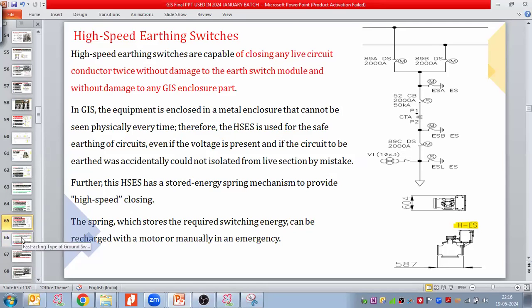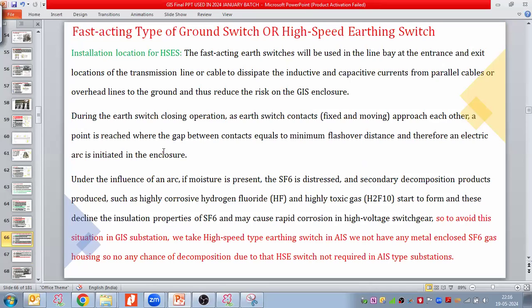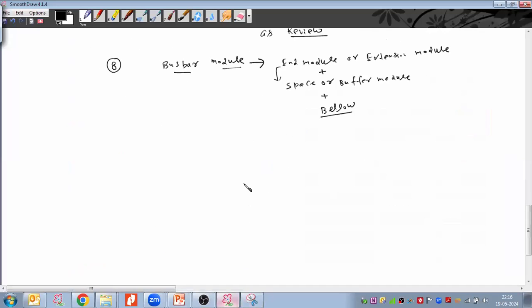Let us take a few more details about the high-speed earthing switch, and where it is required and where it is not required. The installation location of the high-speed earthing switch: the fast acting earthing switch will be used in the line bay at the entrance and exit location of the transmission line. It means it should be in the line bay only, not in the transformer bay, not in the reactor bay, only in the line bay. It dissipates the inductive and capacitive current from parallel cables or parallel overhead lines to the ground, and thus reduces the risk on the GIS enclosure.